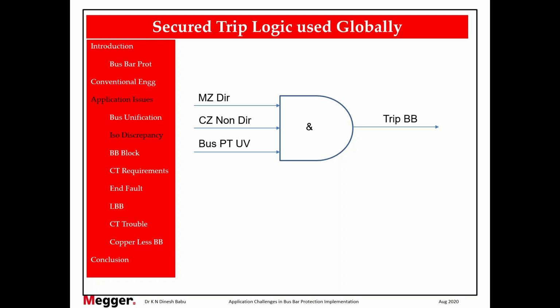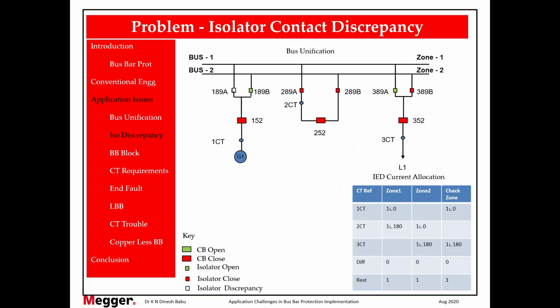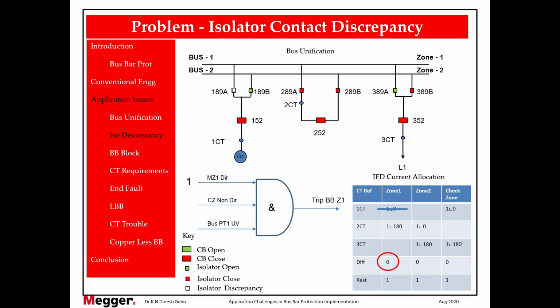So when each zone has this kind of supervision, then we can understand some worst case scenarios. Isolator discrepancy, yes, this is eliminated. Now main zone, in this example, has picked up, let us assume. Check zone will not pick up. Bus PT under voltage will not occur. PT under voltage will occur only when there is a bus fault or some external line fault.